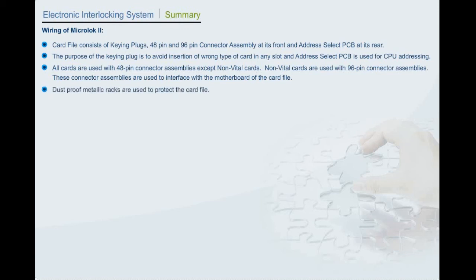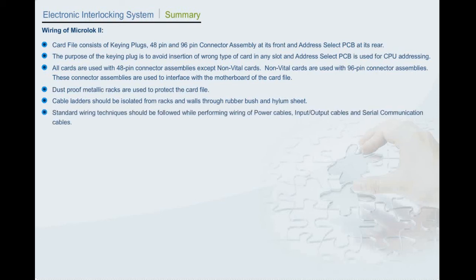Dust-proof metallic racks are used to protect the card file. Cable ladders should be isolated from racks and walls through rubber bush and Hylam sheet. Standard wiring techniques should be followed while performing wiring of power cables, input or output cables, and serial communication cables.